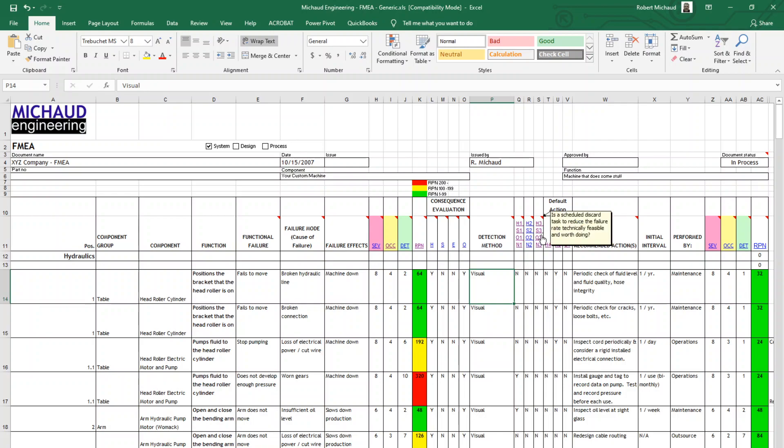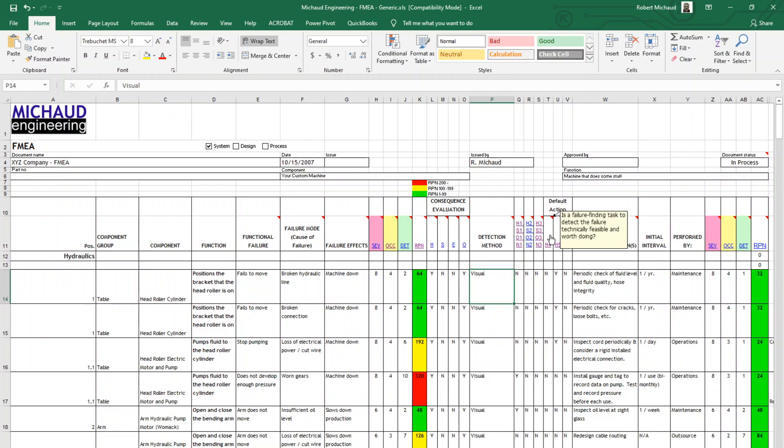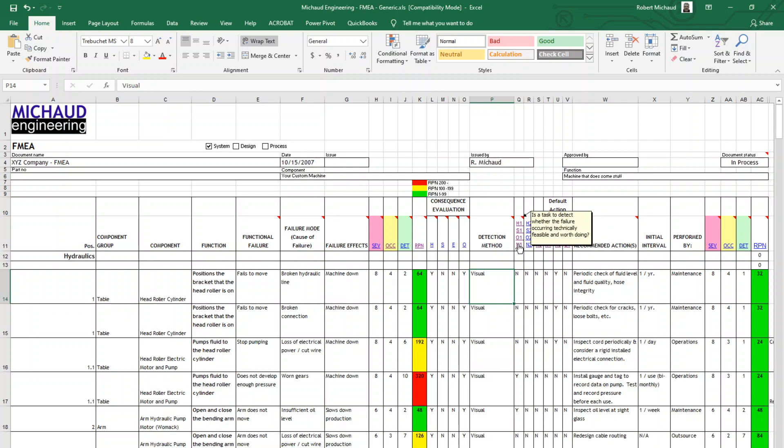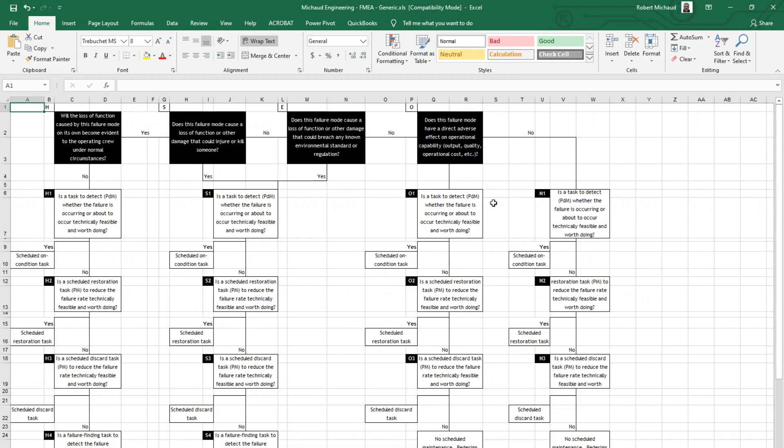Is a scheduled discard task to reduce the failure technically feasible? For instance, if there was a bearing, would it make sense to go in and replace that bearing regardless of whether it's failed or not on a periodic basis to prevent the occurrence of a future failure? And then there's some other default actions here. Is a failure finding task to detect the nature of the failure technically feasible and worth doing? If you'll notice that each one of these has a code next to them, H1, S1, O1, and N1. These all correspond to a decision tree that can be discussed in more detail during an FMEA. But it basically brings you through a decision-making process on each one of those criteria. I'm going to head back to the FMEA chart.